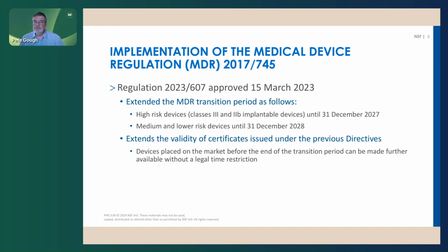For high-risk devices, it was extended until the 31st of December 2027, and for medium and lower risk devices, it was until the 31st of December 2028. So we're still in the transition period, and it extended the validity of the certificates issued under the previous directives, which the regulation had replaced. Again, they were made indefinite until the transition period was complete.